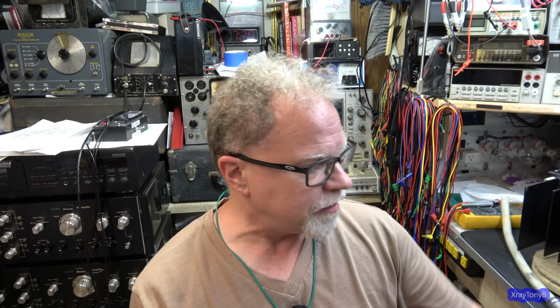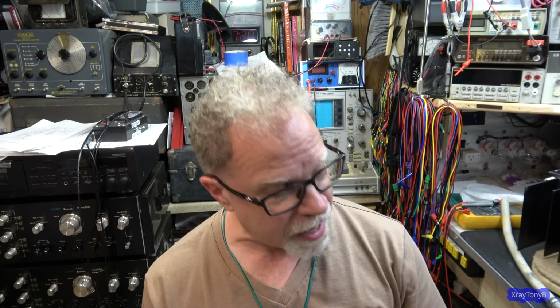Basically, this is a 250 volt maximum fuse. Yes, fuses have voltage ratings. Everybody says it doesn't matter the volts, it's just the amps. Well, yeah, the fuse will fail at that amperage, but it's also dependent on voltage. There are things called breaking current and maximum breaking voltage that you have to think about.